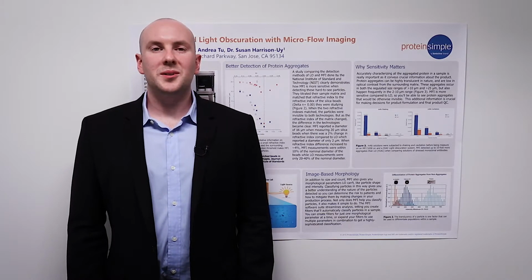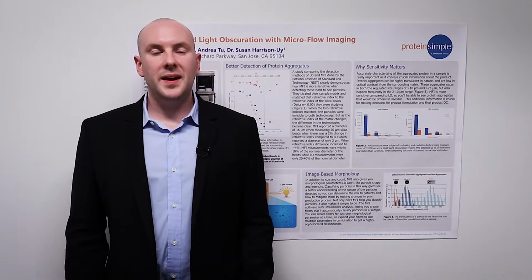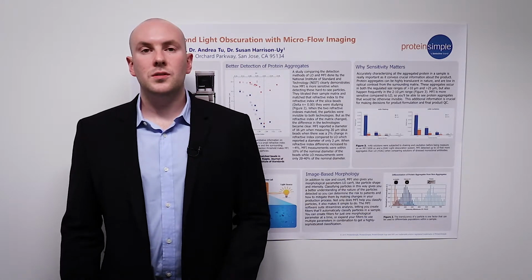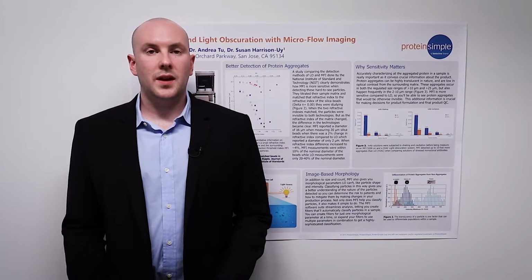So MFI is measuring about 18 microns compared to the nominal diameter of 20 microns, and light obscuration is only measuring 5 microns under those same conditions. This ability to measure particles with low optical contrast to their matrix is especially important for evaluating biopharmaceuticals.